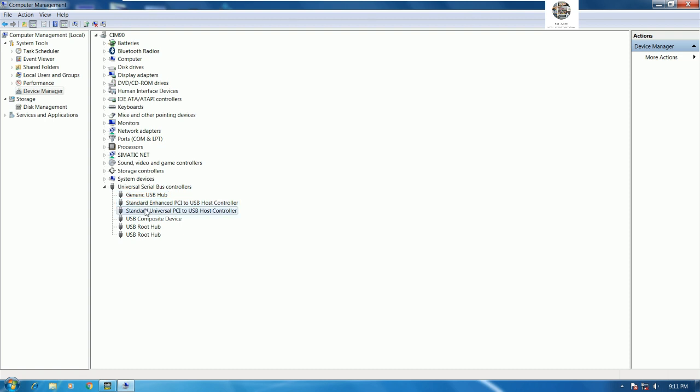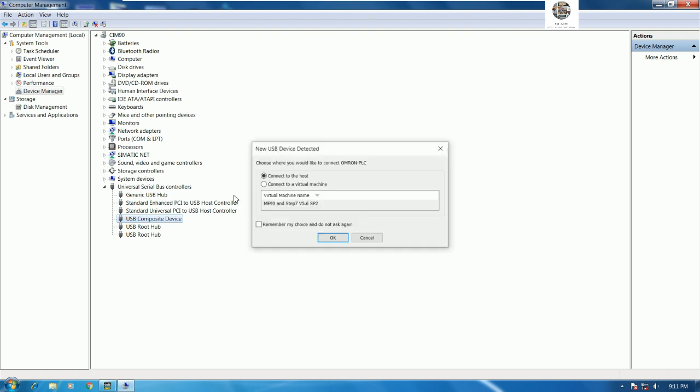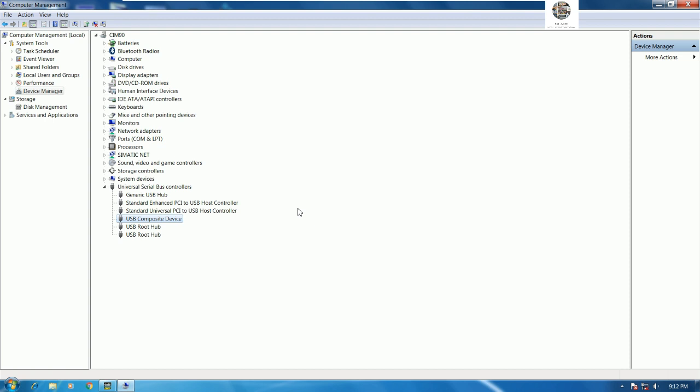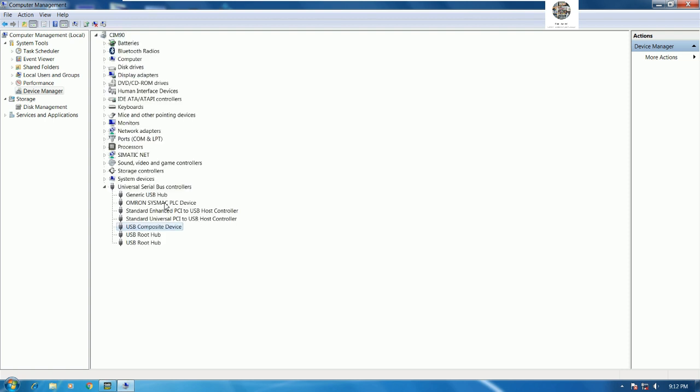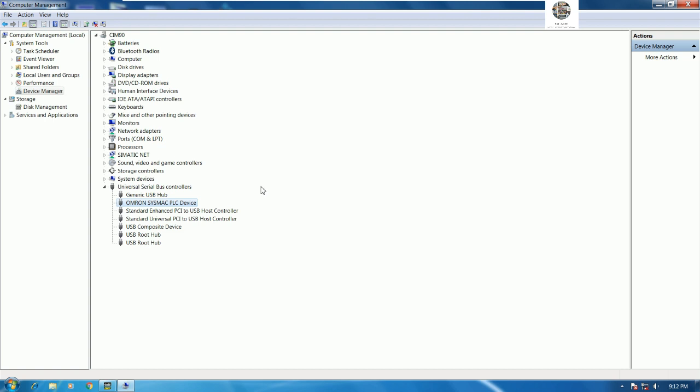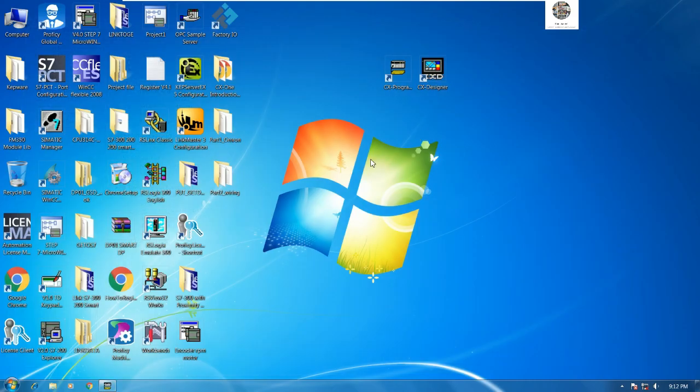Let's check the device here. Omron SYSMAC PLC device. If we disconnect the cable it will be hidden from the universal serial bus controllers. If I connect again and choose the virtual machine, it will see the Omron driver again. Be careful, if we connect the USB from PLC to our computer we must check here before we upload, otherwise we cannot upload from the PLC.